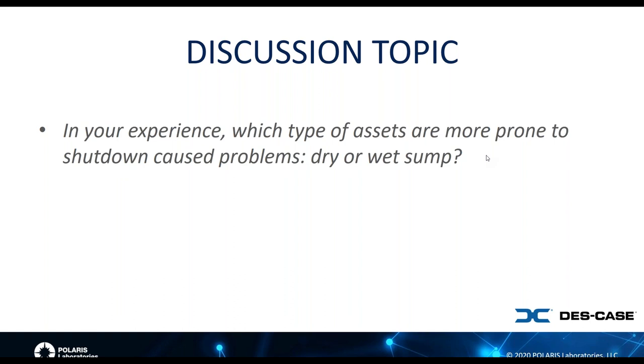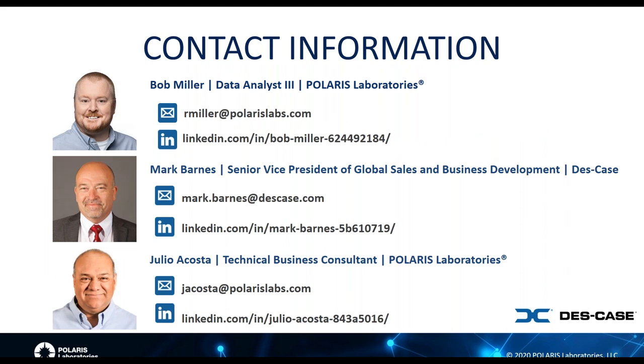Yeah, I mean, obviously, first look at critical assets. Think about the potential failure mechanisms that can occur in critical assets. So if you're an injection molding plant, as an example, think about the health of the fluid and make sure that you know that fluid is healthy before you start. Contamination is 80 to 90% of all mechanical issues in lubricated systems. So think about whether the oil is clean, whether it's dry, whether the oil is still healthy for continued use, and use shutdown as an opportunity.